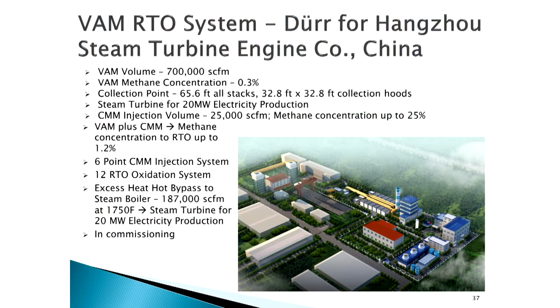And that, again, is a very, very specialized mixing system that has to achieve very, very high mixing efficiencies and be proven out through CFD modeling, because obviously if any of that 6% concentration methane stream somehow sneaks through that air blender, we've got a serious situation on our hands at the RTO. So in this case, we're sending about 187,000 SCFM at 1,750 degrees to the steam turbine, and we're doing about 20 megawatts of power there.